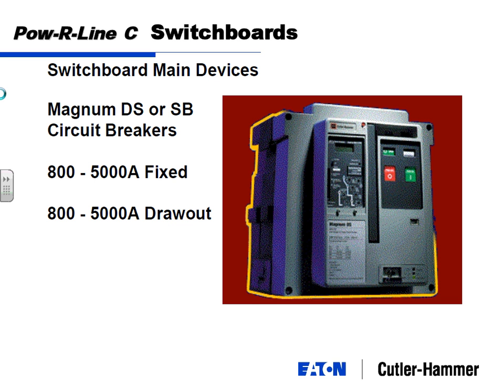As a common rule, you always want your circuit breaker closest to the fault to be the one that trips. Just from common sense or practicality, if I have a fault here and I have a choice about shutting down the power to this room, this floor, this building, or this block, I'm probably going to choose this room. It's not always feasible, but that's what you always prefer. So switchgear has the benefit of sitting there, letting things downstream trip if possible, and if they don't trip, then it trips.